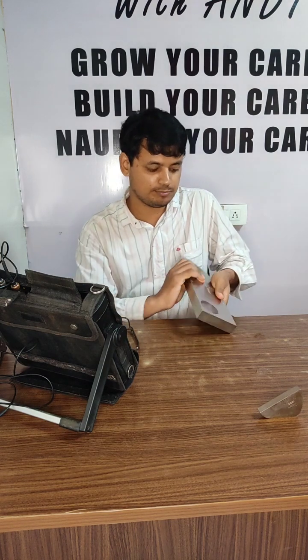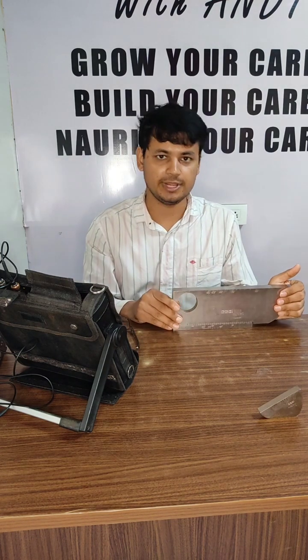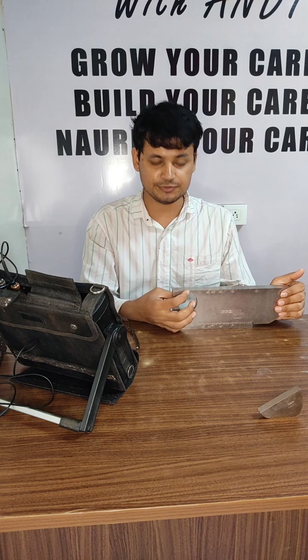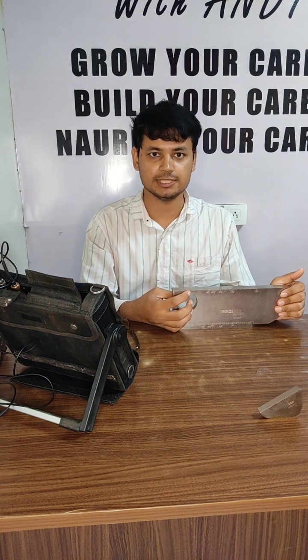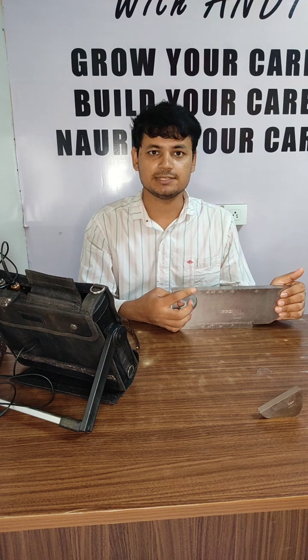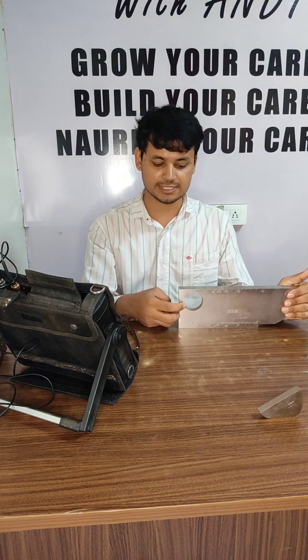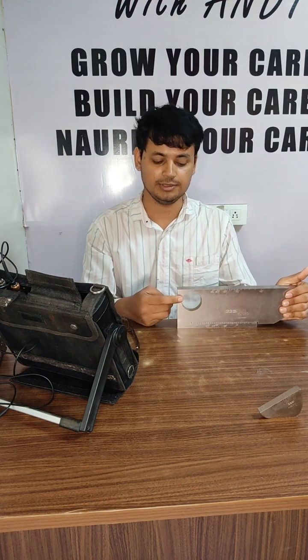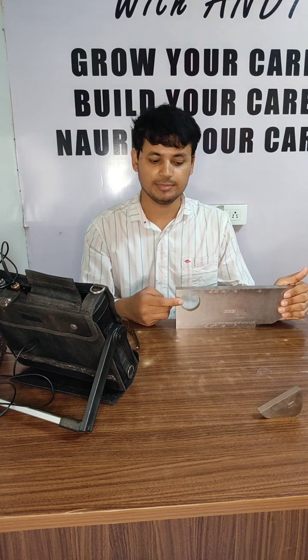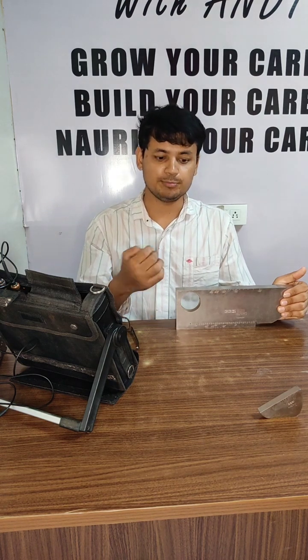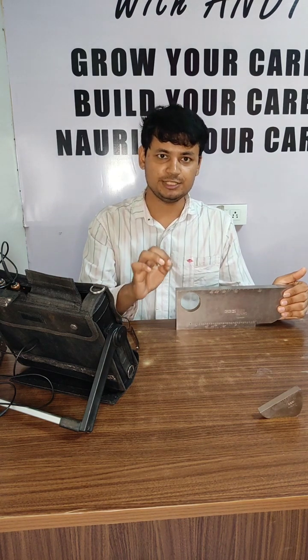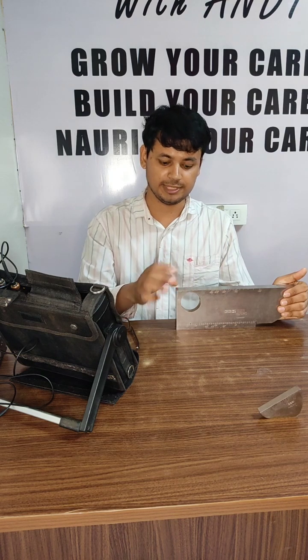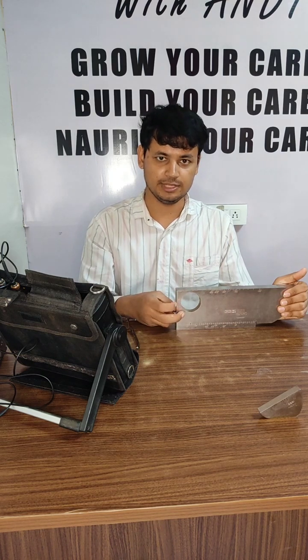let me just put it up over here. All right. The distance you are seeing from the top to this arc, this curvature, is 5 mm, and this distance over here is 10 mm. You are calibrating the probe. If you want to check the dead zone, we use this 5 mm and 10 mm, as you can see on the screen.